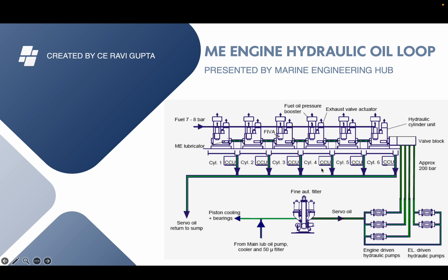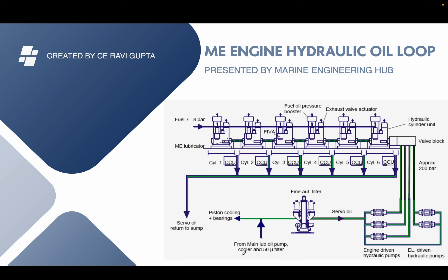Before talking about the Auxiliary Control Unit, first we need to understand how this hydraulic loop works. From the main lube oil pump, pressure is developed around 2 to 4 bar and that pressure is coming in. A part of it is going for piston cooling and bearing lubrication. A part of the oil is going to the auto backwash filter, which has a filtration unit of around 50 micron.